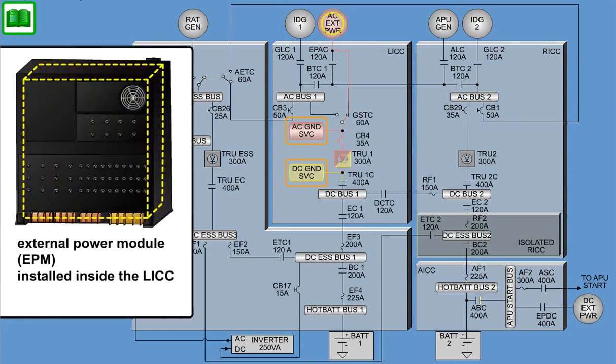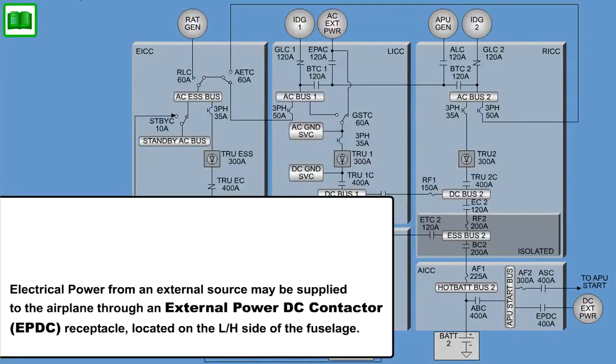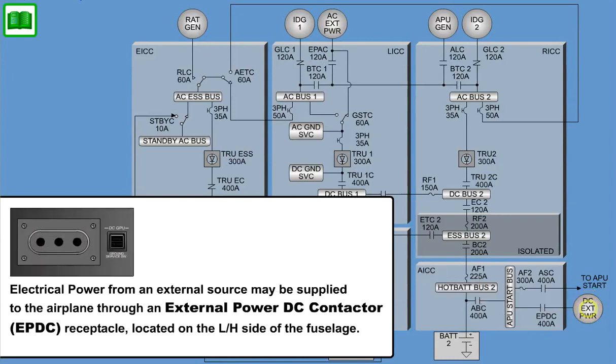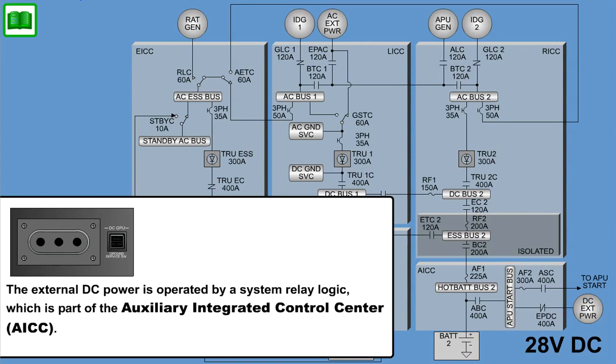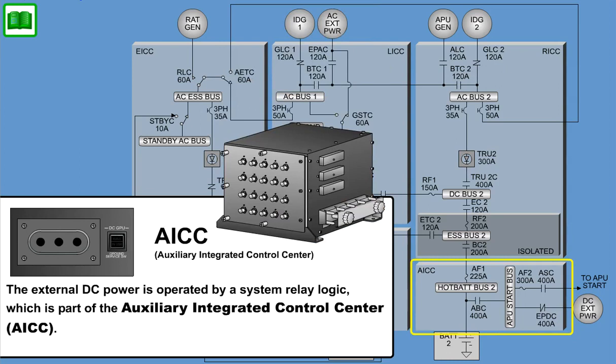The operation of the system is controlled by the external power module, EPM. Electrical power from an external source may be supplied to the airplane through an external power DC contactor, EPDC, receptacle, located on the left-hand side of the fuselage. It allows 28-volt DC to be supplied to the APU start bus for APU start. The external DC power is used to power the APU start bus.